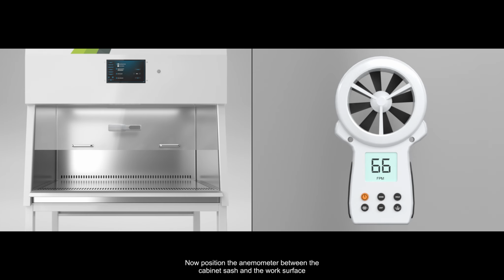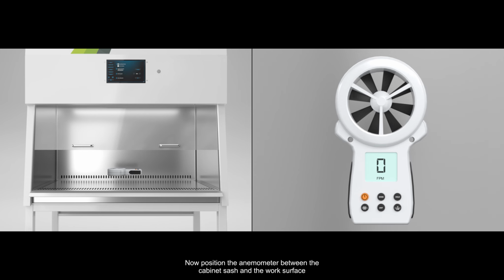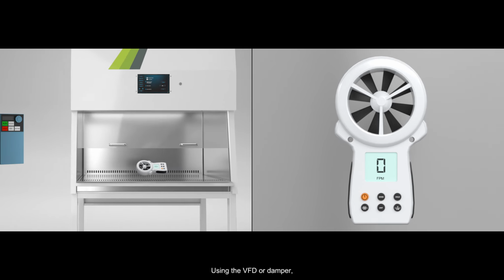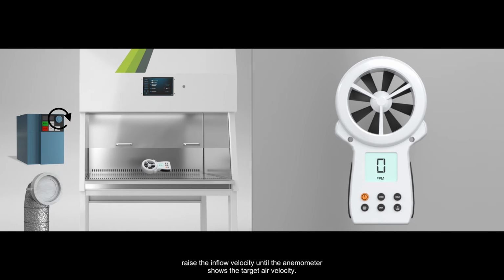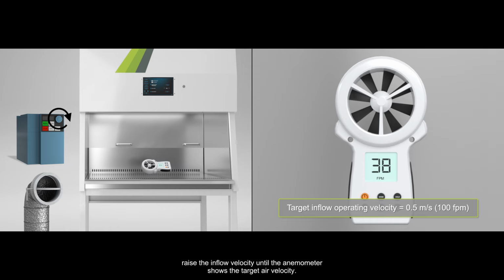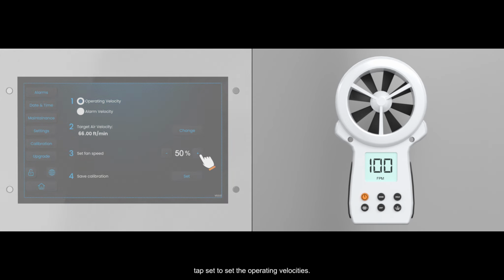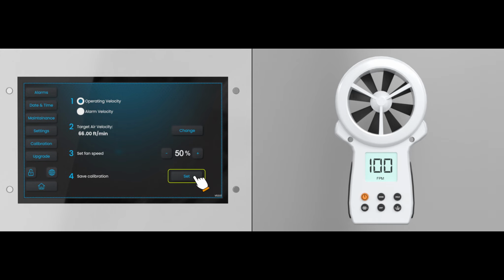Now position the anemometer between the cabinet sash and the work surface and tilt the anemometer to a 45-degree angle towards the back of the cabinet. Using the VFD or damper, raise the inflow velocity until the anemometer shows the target air velocity. When the measured downflow and inflow reach the target air velocities, tap Set to set the operating velocities.